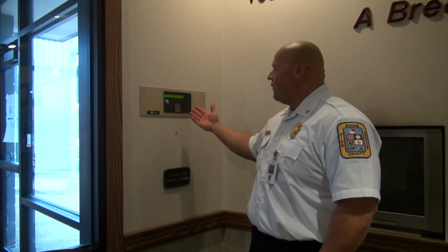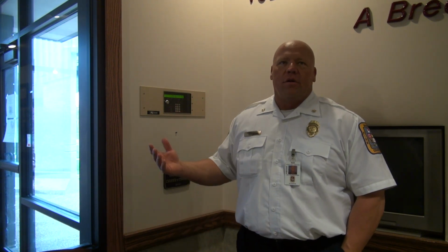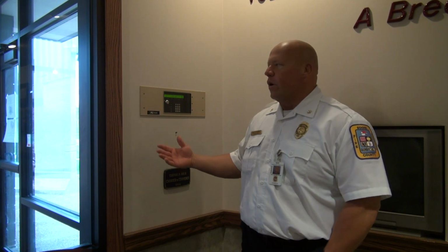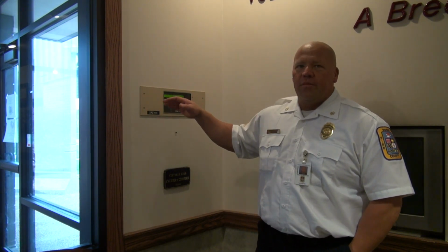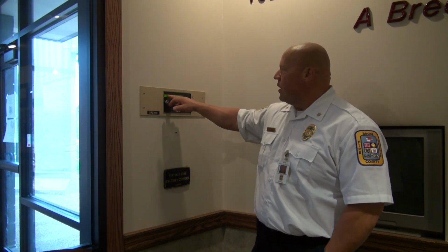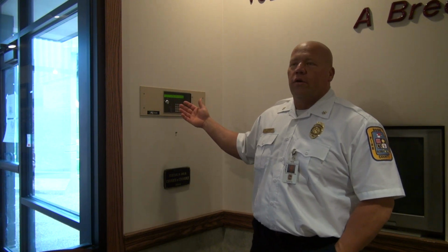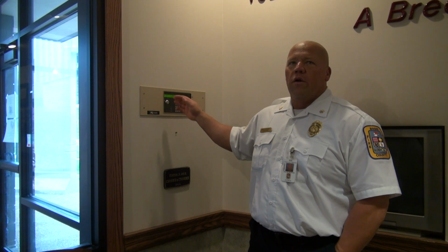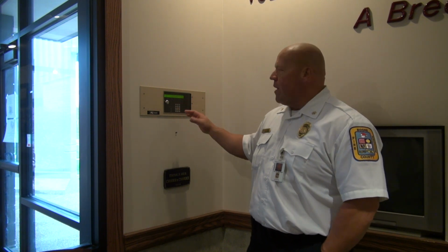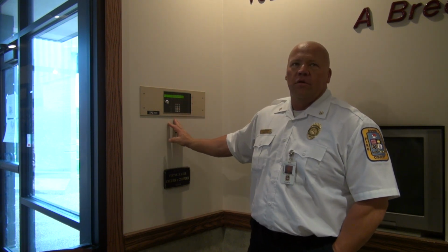Okay, so we've made entry into the building. We've accessed the fire annunciator panel, which is just an alarm panel indicator. It tells you what's going on inside the building. So if we were dispatched to a true general fire alarm, it may just say general fire alarm. Typically these are an addressable system, which will give you an indication of where the alarm is coming from. There may be a map showing you the zones.